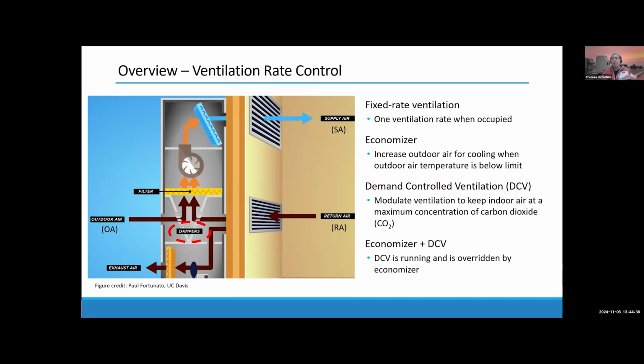The really big problem with this strategy is it doesn't consider the implications of outside air pollution. So on a cold winter morning, when there's an inversion or there's wildfire smoke present, those outdoor air dampers will all open all the way and bring a bunch of pollution into the building. And facility managers that have some central controls may be able to temporarily, manually override those things. But, essentially, there's got to be a better way, right?